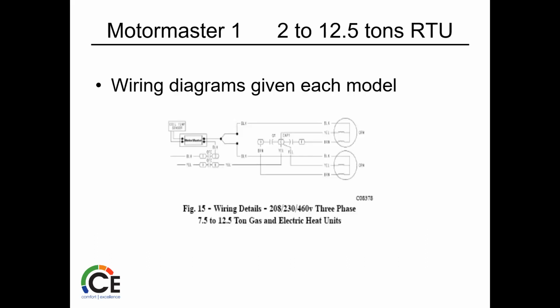It's not the best picture, I'm sorry. But again, we're just going to hook this up, and we're going to start to control that outdoor fan. So we're going to run power into the control and then back out to the fan, so that if it engages, it shuts the outdoor fan down. And then of course, we get our temperatures up a little better and we get some cooling.